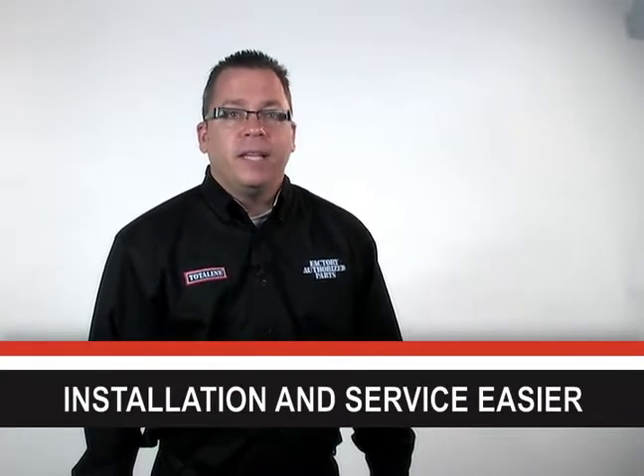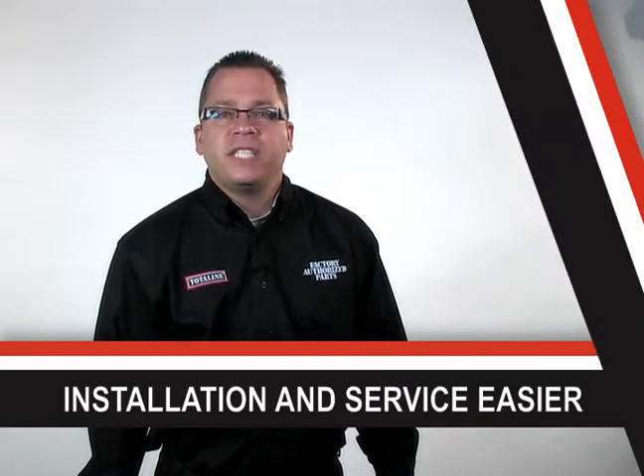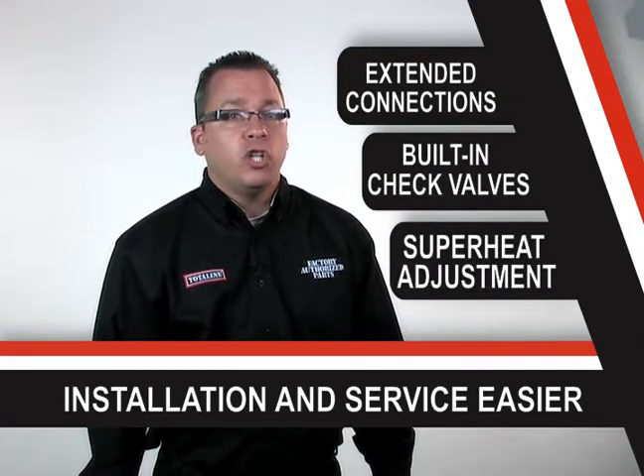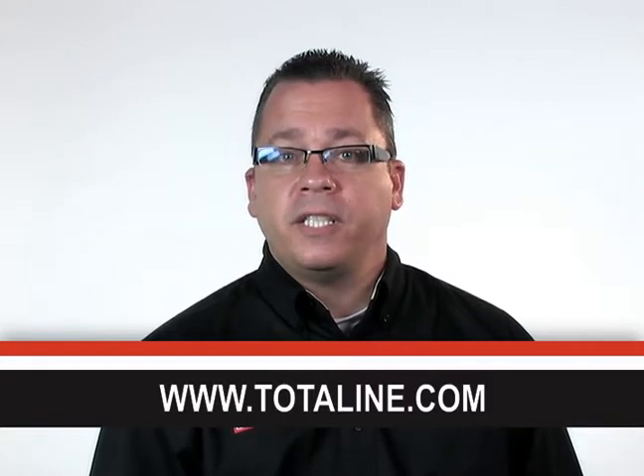Performance, reliability, and safety are all very important to your customer. But what can choosing factory authorized parts TXVs do for you? They make installation and service easier. These TXVs always match the Carrier, Bryant, and Payne system design requirements. The majority of valves have extended connections, which makes brazing much easier. In addition, they have built-in check valves to assure bi-flow capability and superheat adjustment, so you don't have to worry about settings. It's clear that factory authorized parts TXVs have a lot to offer over aftermarket TXVs. If you visit Totaline.com, you could be eligible for free merchandise and special offers when you buy them.